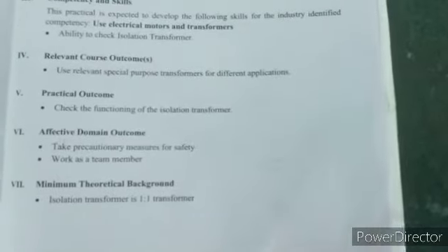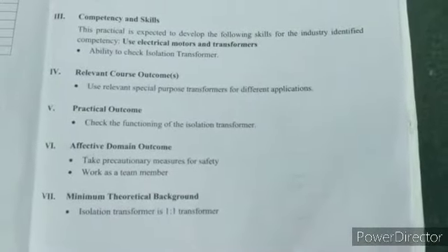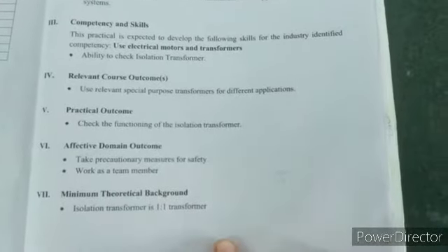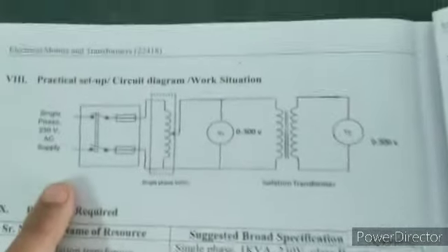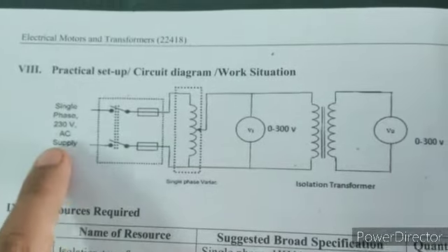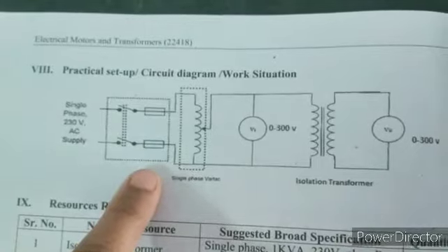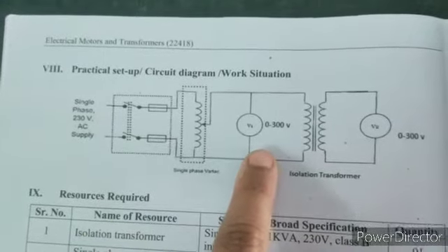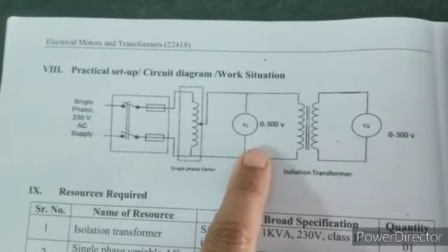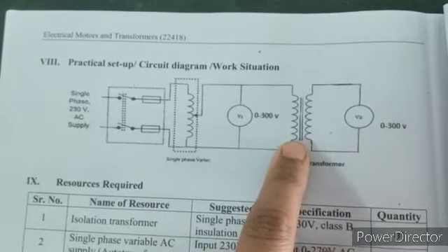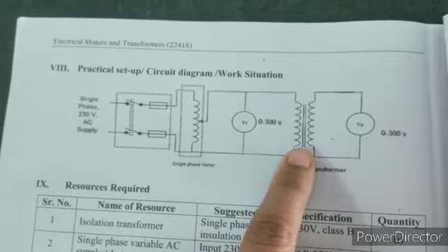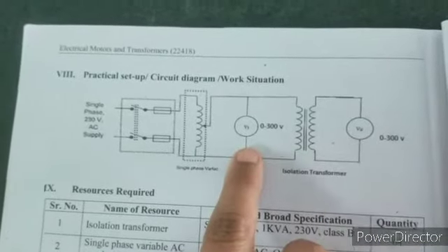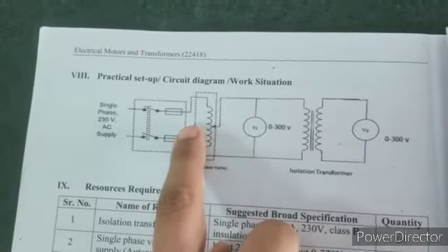What is called an isolation transformer and what is its function? Isolation transformer is a 1:1 transformer in which whatever voltage you give on the input side, you get the same voltage on the output side — which we are going to see in this practical. This is the circuit diagram of isolation transformer. You can see single phase AC supply is connected to our single phase variac. Single phase variac is also called auto transformer. Voltage source is always connected in parallel in the circuit diagram. This is the symbol of the transformer — a one-to-one transformer — where voltage is connected in parallel on the primary side and a voltmeter is connected on the secondary side, with one connection going to the common of the auto transformer.